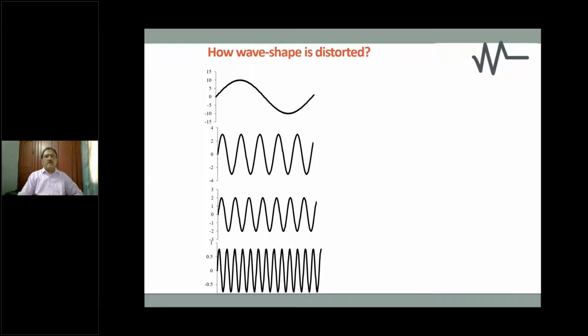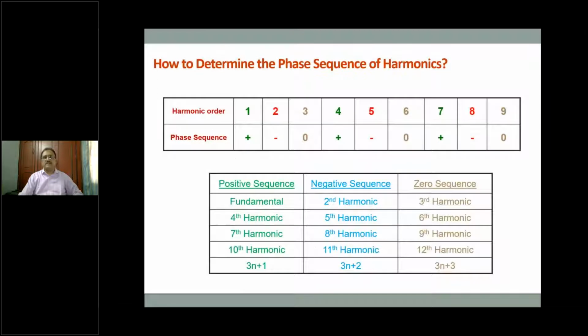So typically, when an equipment is using multiple orders of harmonics, all these harmonics will get superimposed. See 1, 5, 7, and even more, and they will take a shape like this. So if you use a power quality instrument to measure harmonics, you will find that the wave shape has become like this. What was supposed to be a simple sinusoidal wave shape has become like this. So this is the impact of harmonics in the system.